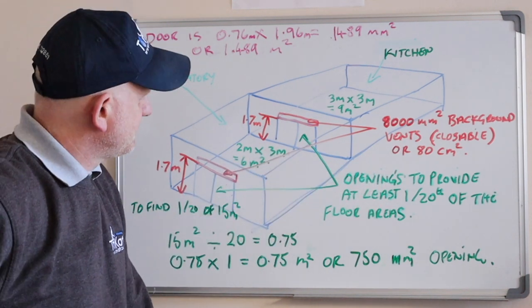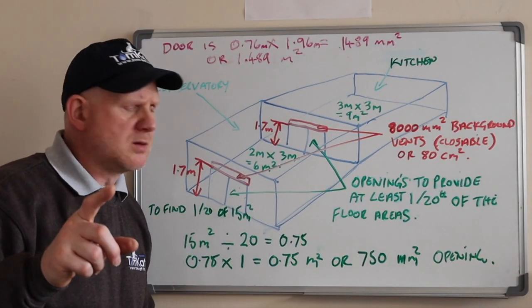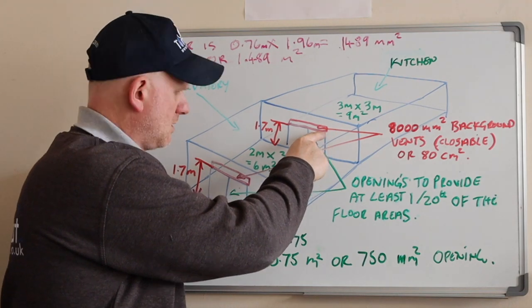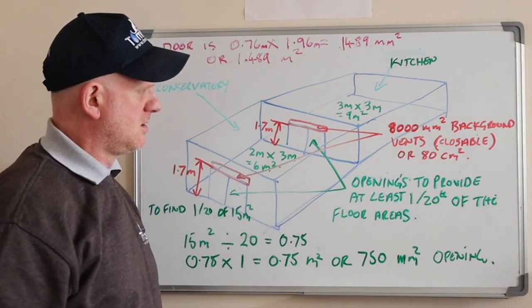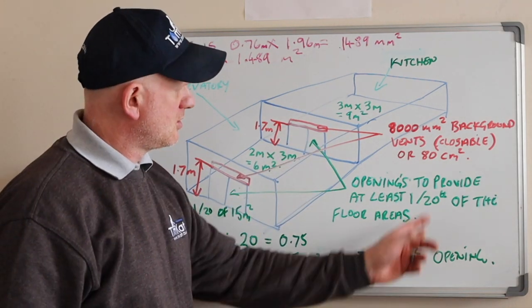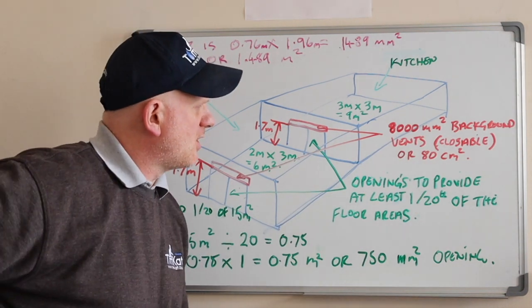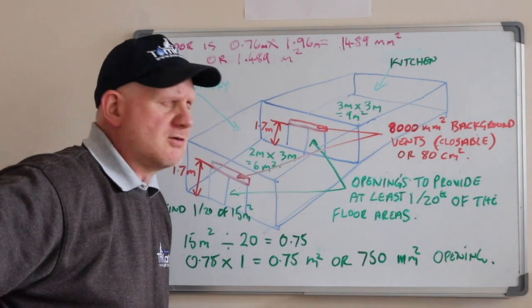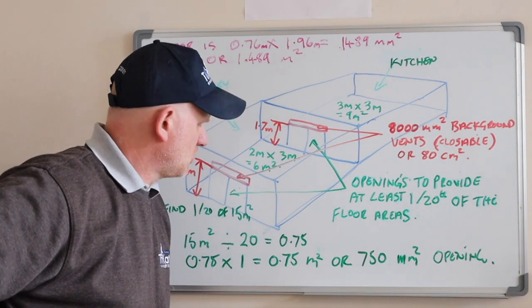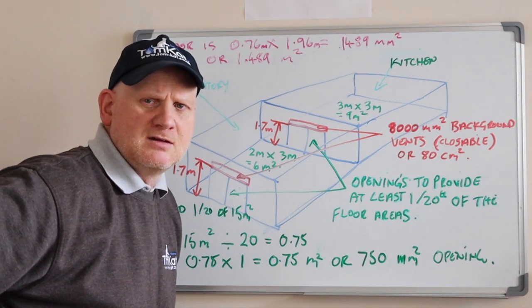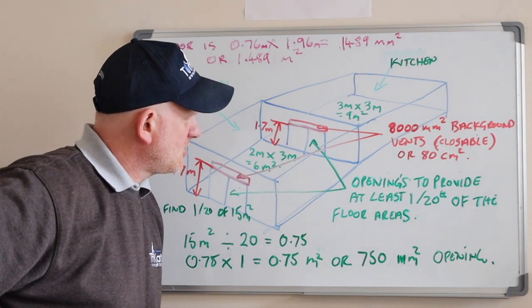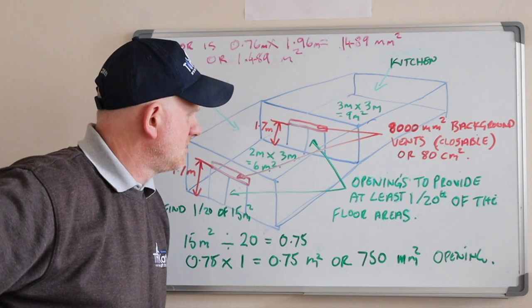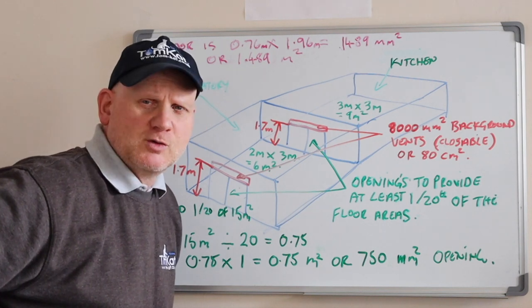If you had a window in the kitchen wall to the conservatory and a window in the conservatory wall to outside, and when opened they provided more than 80 centimetres squared — the Building Regs do say it has to be openable, so arguably you could use a window for that purpose.